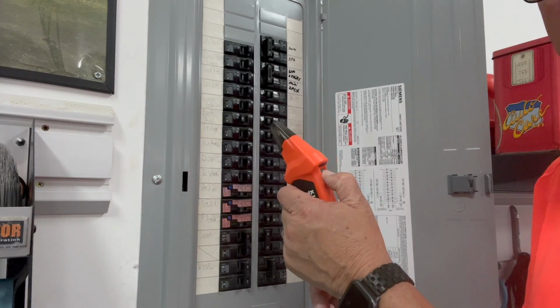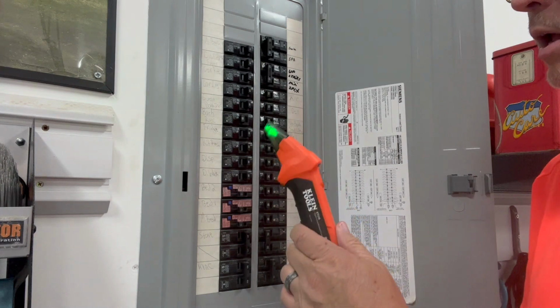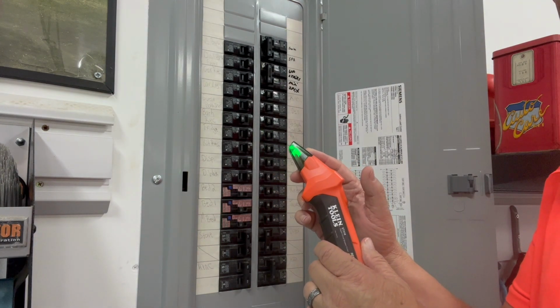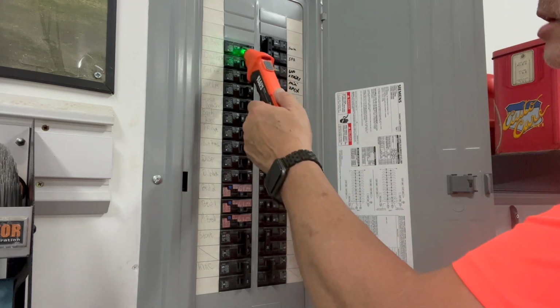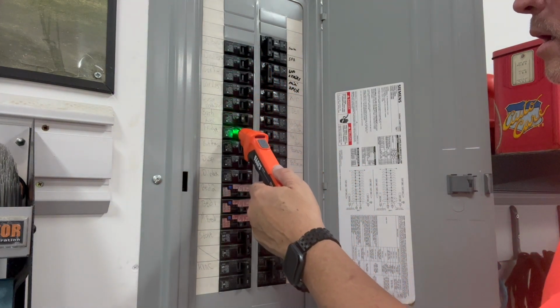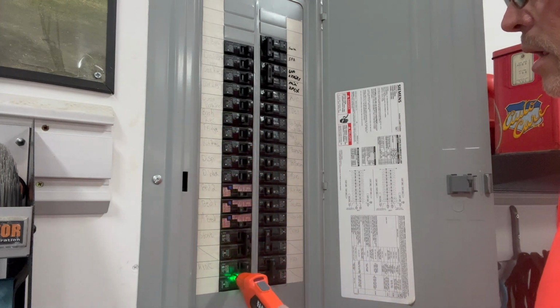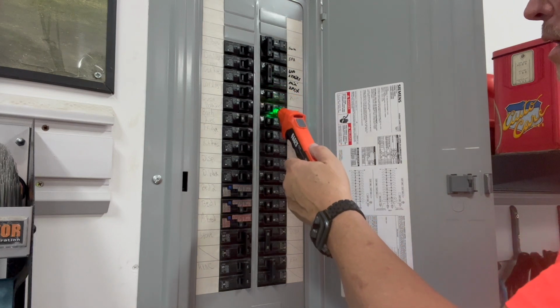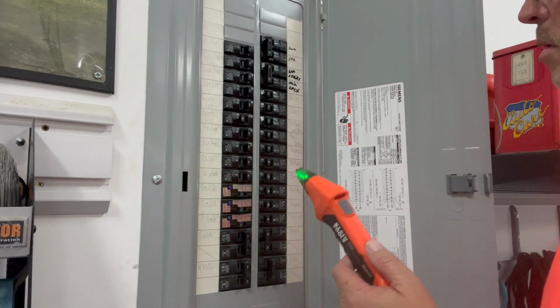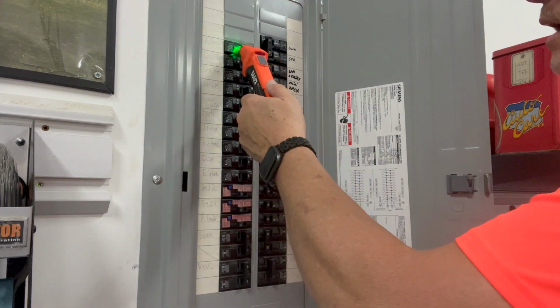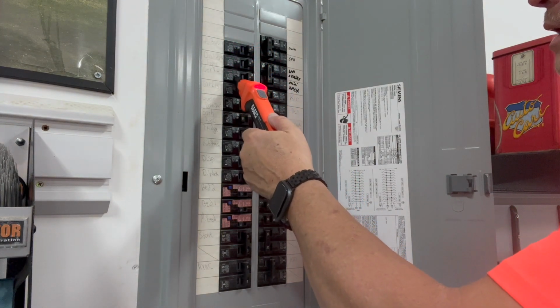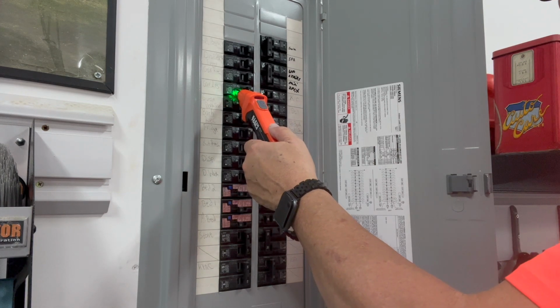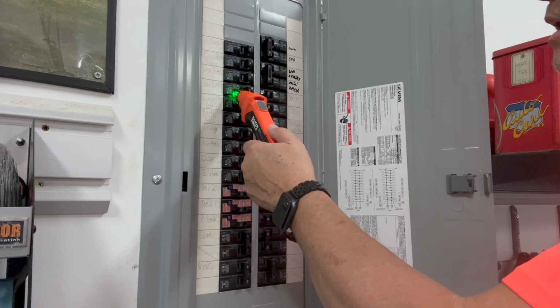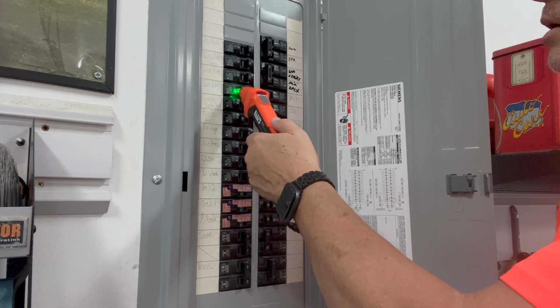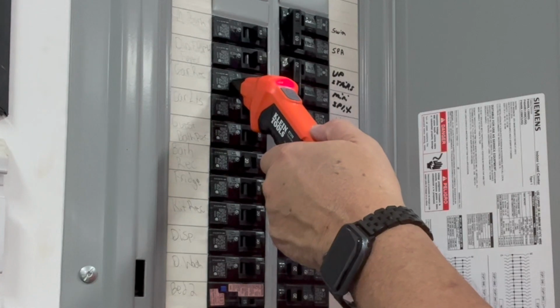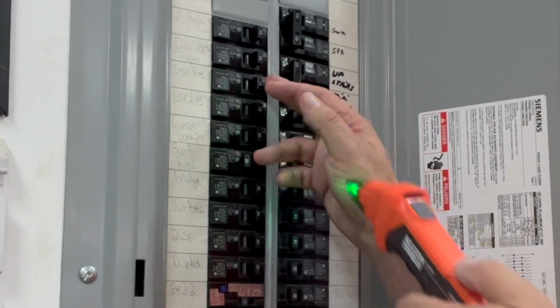Okay, to test, you want to turn your scanner on by pressing the on-off button. You can see the green indicator light, and you have just kind of a steady rhythmic beep. You just start at the top and you're scanning your way down. And what you're doing is learning first on the first scan, okay, and then you lift off a little bit and scan the second time to indicate which circuit. So you scan to learn the first time and scan to identify the second time. So you can see this circuit here is the one that's being identified as red.